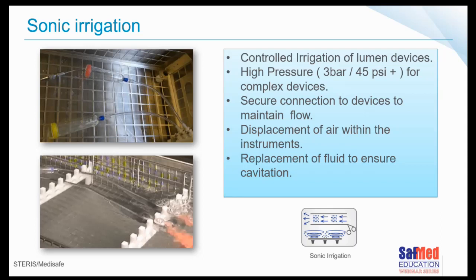You're looking at using controlled irrigation, and the irrigation is going to be at a different measurement, normally measured in PSI, for example. I'm used to 45 PSI to be able to irrigate nicely. And with that, you're displacing the air out of the instrument, now replacing it with fluid, and in that you're going to ensure cavitation. So cleaning the outside of the instrument, but doing a sonic flush down the lumens as well.